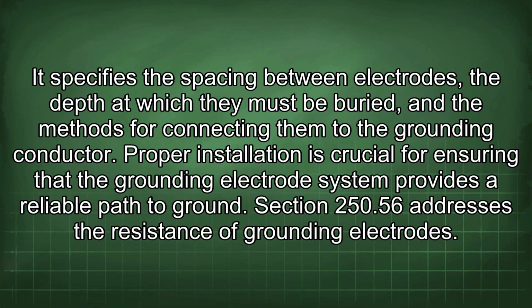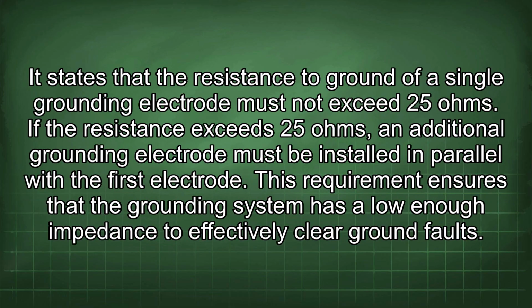It specifies the spacing between electrodes, the depth at which they must be buried, and the methods for connecting them to the grounding conductor. Proper installation is crucial for ensuring that the grounding electrode system provides a reliable path to ground. Section 250.56 addresses the resistance of grounding electrodes. It states that the resistance to ground of a single grounding electrode must not exceed 25 ohms. If the resistance exceeds 25 ohms, an additional grounding electrode must be installed in parallel with the first electrode. This requirement ensures that the grounding system has a low enough impedance to effectively clear ground faults.